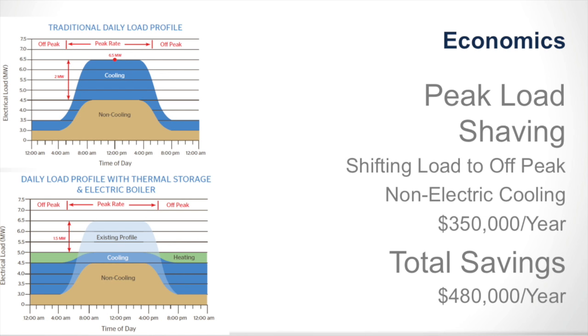So automatically, we lower our cooling cost by a third, 30%. Secondly, at night, the approach temperatures on the chillers matter - any air conditioning equipment's efficiency is dictated by the temperature you reject heat to. The cooler it is outside, the more efficient your air conditioner is. It's cooler at night, so we get cheaper electricity and a more efficient machine. We're able to create cooling for the campus at about half the cost at night as it costs during the day. So if we shift this entire load, we cut that cost by 50%. Just a different way to do some stuff.